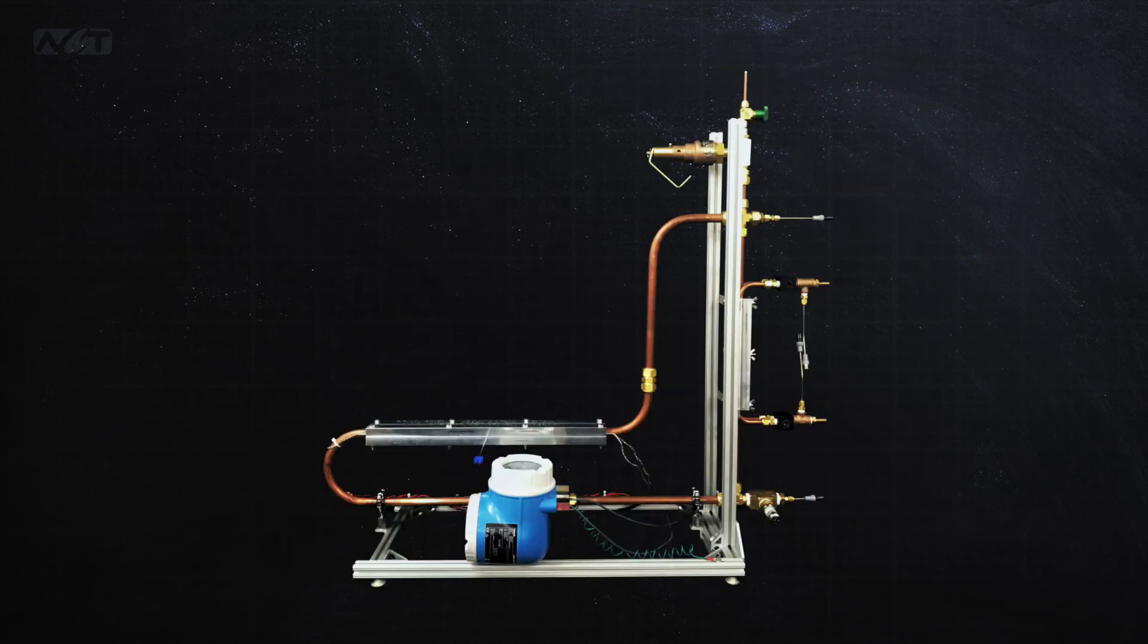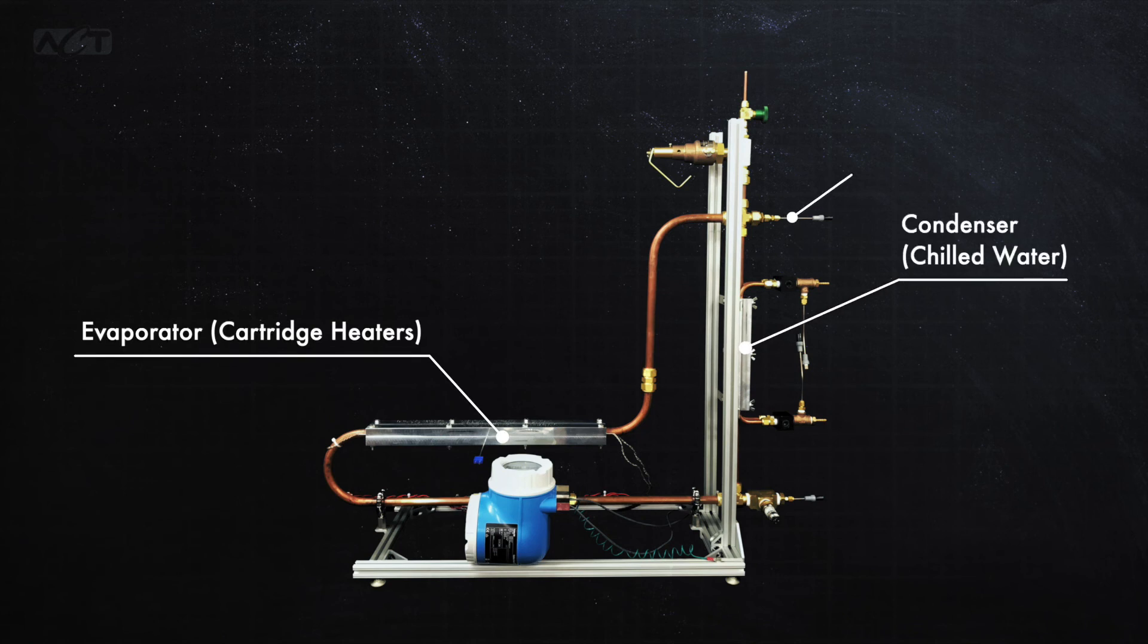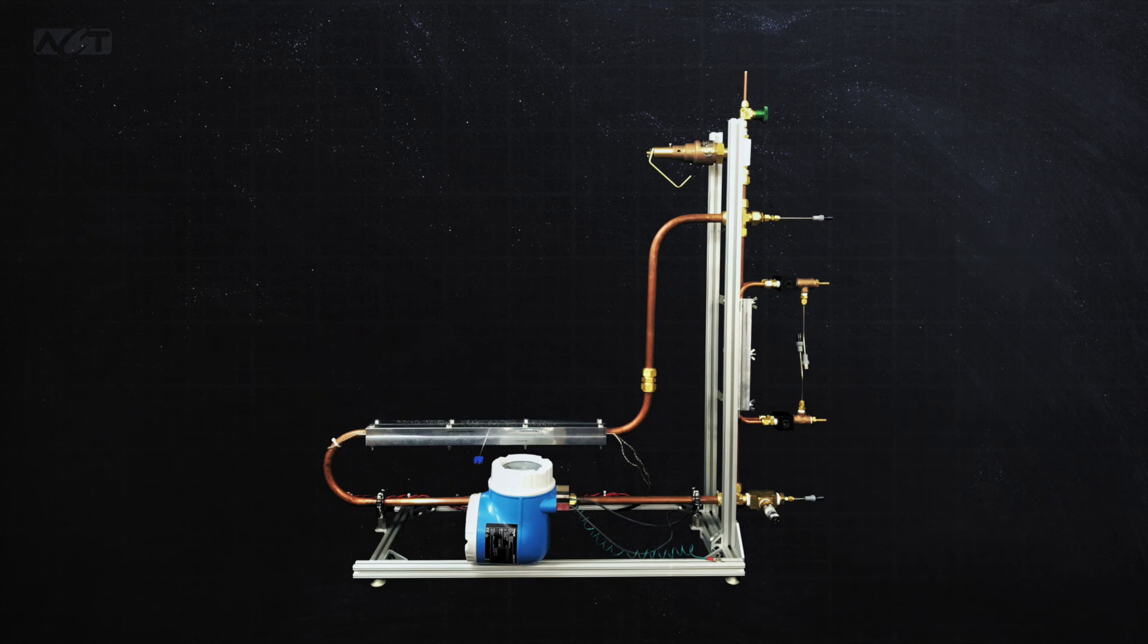The model was used to design the lab-scale loop thermosyphon, which was constructed, instrumented, and filled with water as a working fluid. This loop was heated by cartridge heaters and cooled by chilled water. We used some RTDs for temperature measurements, an absolute pressure transducer for pressure measurement, and an electromagnetic flow meter to record the flow rate.